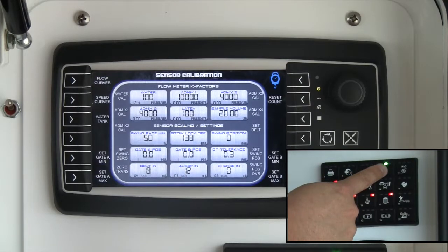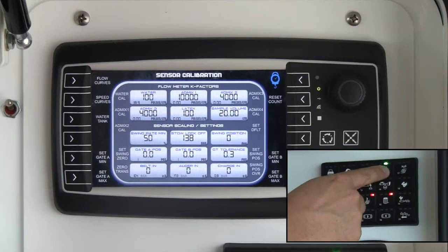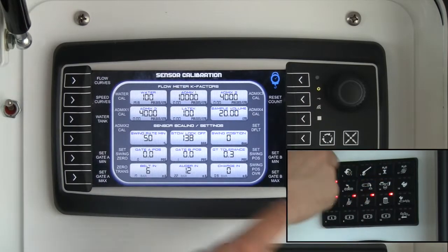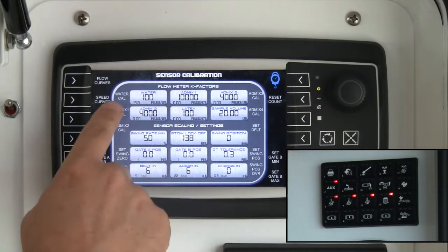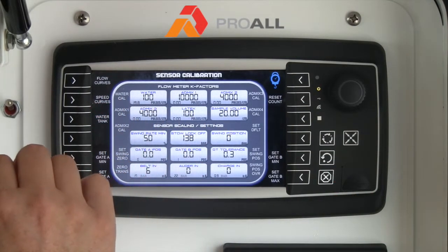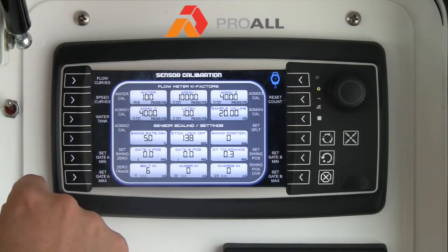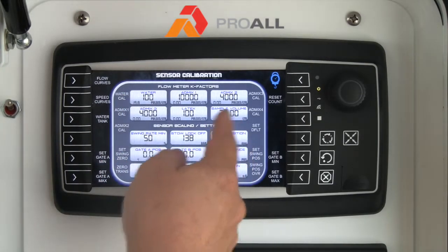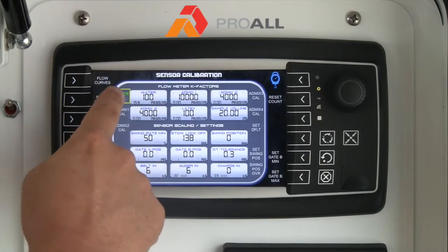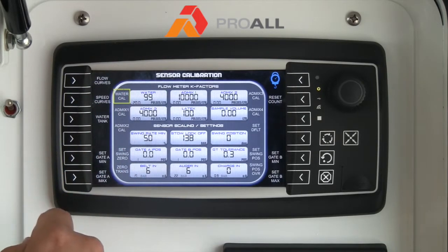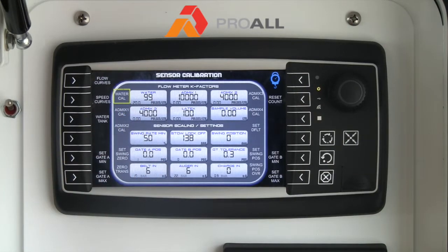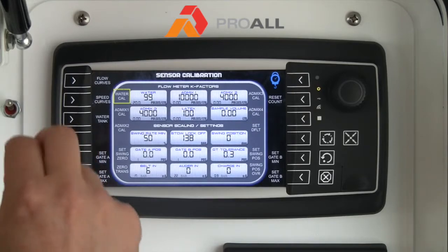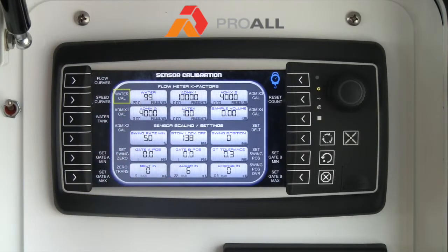We'll stop it when it's around 19 or 18. The totalizer is showing 19.8 liters. We actually took a sample and it was 20 liters. If I hit water calibrate, it automatically adjusts the total to 20 liters and the K-factor, or the calibration value for the flow meter, to 99 from 100.